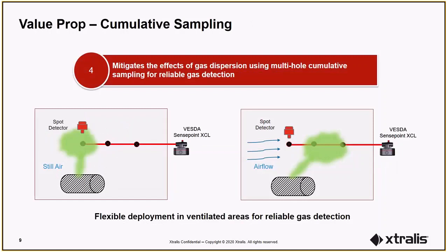With multi-point sampling, VESDA Sensepoint XCL is better suited to detect gas in variable airflow environments. While airflow could push a gas cloud away from a spot gas detector, a multi-hole sampling system would be more likely to detect the gas.